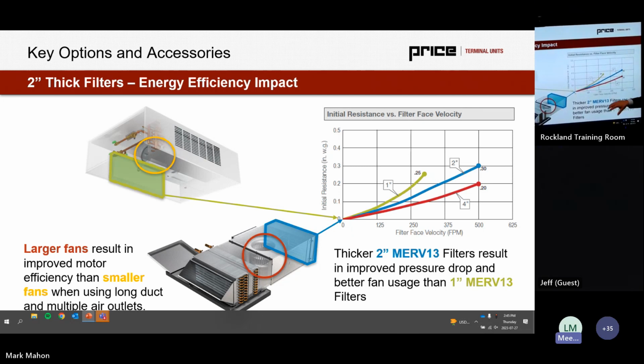The other thing we do with all these products is we throw the biggest possible blower we can, because most blowers are happiest and healthiest running at about 1,000 RPM. So we can even see with our low profile fan coils, we get a big clamshell blower that has a tighter kind of profile. We flip it on its side and we situate it in the unit like that instead, which allows for much better fan operation as well.